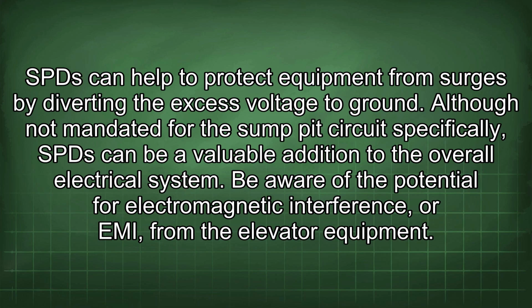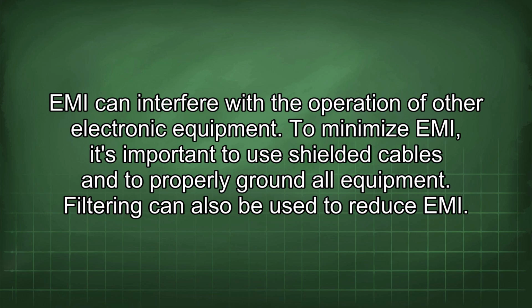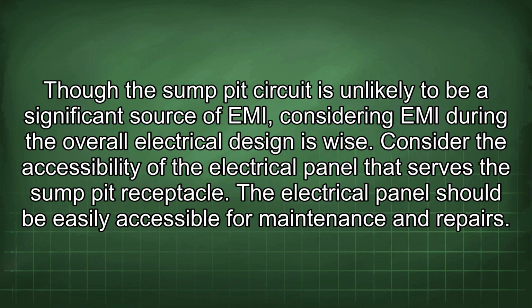Be aware of the potential for electromagnetic interference, or EMI, from the elevator equipment. EMI can interfere with the operation of other electronic equipment. To minimize EMI, it's important to use shielded cables and to properly ground all equipment. Filtering can also be used to reduce EMI. Though the sump circuit is unlikely to be a significant source of EMI, considering EMI during the overall electrical design is wise.